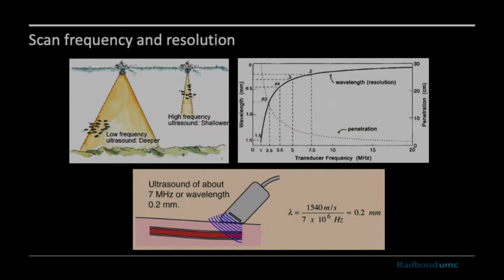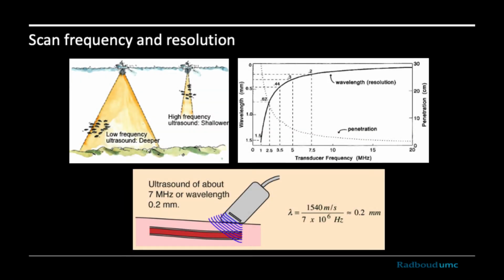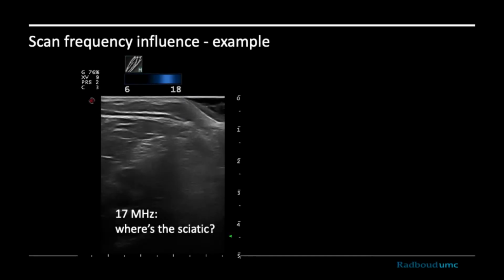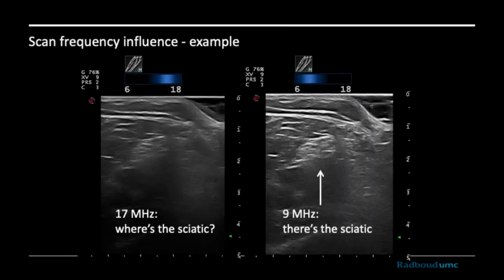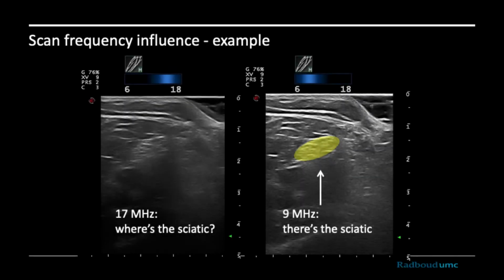So here's an illustration about the relation between scan frequency and your resolution. Higher frequencies will give you a lot of detail in the image, but low frequencies are needed to get to deeper parts. So optimally, your probe will have a combination of both, and you need to choose the correct frequency range for the image you need to create. Here's an example. This is a 17 megahertz scan of the sciatic nerve at the level of the knee, but you can't really see the nerve right here. And it only comes into view when we add a lower frequency setting, such as this 9 megahertz setting. And then you can see the nerve pretty well because it's a little deeper at 2 centimeters. Now, if you hadn't seen the nerve already, it's highlighted in yellow here.